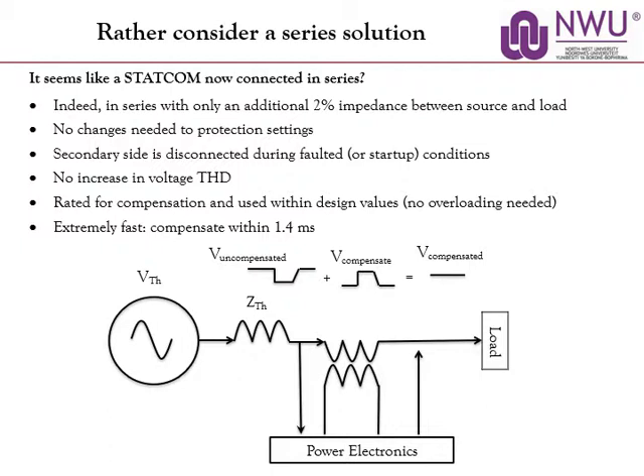So the moment something goes wrong in the system, this part is short-circuited, first by a thyristor that fires extremely fast, handling huge overcurrents until mechanical lockout kicks in. It doesn't cause any increase in voltage total harmonic distortion, and the equipment here is rated for the compensation and used within design values. No overloading is needed. And it is real fast. 1.4 milliseconds. In the 20 millisecond cycle, the load will not even know anything was wrong.